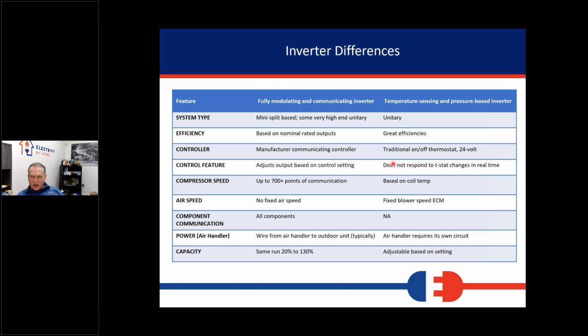That inverter works off of the temperature of the indoor coil. In other words, the air passing from your house goes through the coil. The coil temperature is set by the refrigerant going through, and it has a sensor on there that can automatically adjust to the load. So as your house gets a little cooler, the load on the coil reduces, so the system slows down. There's not a way for you to make an adjustment mid-cycle or anything on that type of system.